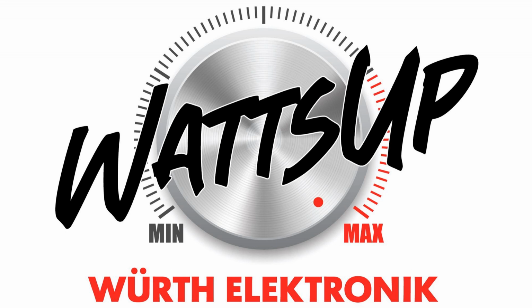So as you can see, we are clearly above the limit. I can also check it with our function, the list of maximum emissions. It will mark all of the emissions here, all the points, but I clearly see that I'm failing the EMC test. So I have to do something. The common thing is that you use a power line filter. So first of all, I'm going to save these measurements if I want to see them later. And I will write quasi-peak and average with no filter. You can save in different options. I'll just use the CSV file and save it. And later on, we will compare.